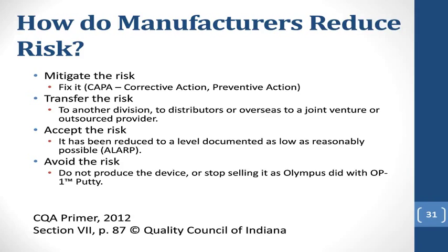And you will see that almost any kind of medical device that's out on the market is out there because there's a market for it, which means it has competitors. And if you go through and review documents where they talk about the identified hazards and how to manage the risks of devices, you'll look at the competing device, and it may be a very different approach. And that's why you really need to have an understanding of how manufacturers look at risk and identify it and potentially mitigate it or avoid it.